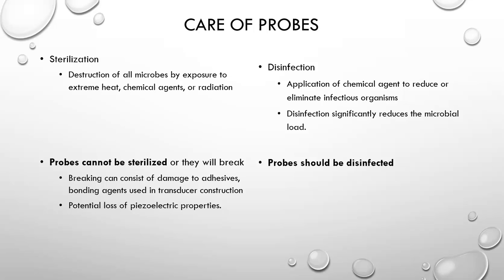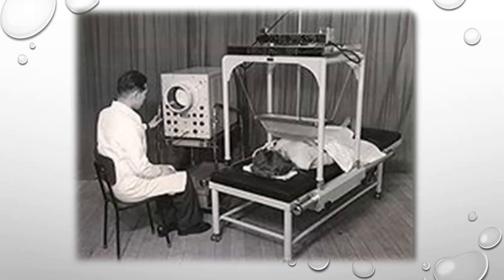Disinfection is the application of chemical agents to reduce or eliminate infectious organisms. Disinfection will significantly reduce the microbial load. Ultrasound probes cannot be sterilized. They will break. Usually when they break, the adhesives that hold them together come apart and no longer work. Ultrasound probes must be disinfected. Here is an early ultrasound probe. I'm sure they're having a fun time cleaning that one when they're done.